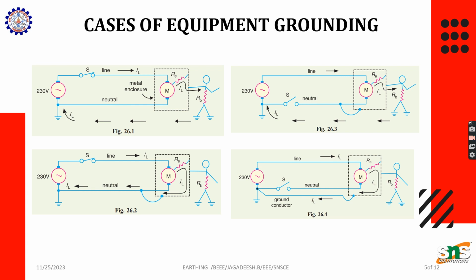So let me consider the example in figure 26.3. Here, as I mentioned, the enclosure of the motor is connected to the neutral. In case the neutral is turned off, or a mechanical injury makes the neutral open, the human body will definitely get the shock. So we have to connect like figure 26.4. We connect the neutral wire to the grounding, and the enclosure of the motor to the grounding separately, so that if the neutral is cut, the direct grounding from the enclosure will prevent the shock to the human body. So we always prefer figure 26.4.